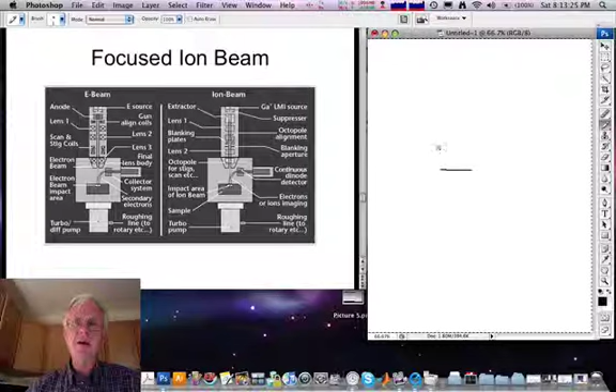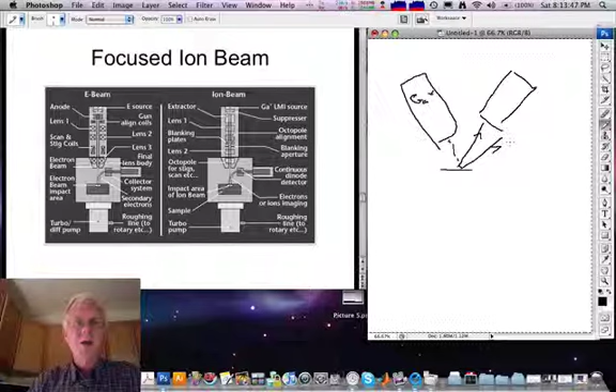And in the instrument that we have, they actually have two beams. So a sample sits like this, and then in one direction an ion beam comes down and mills the sample. So gallium ions, and then in another direction an electron microscope images the area being milled at the same time that it's milled. So the source of gallium is shown here. It's a little filament on which is suspended a gallium source in this container here, which is both heated and ionized to form the beam of gallium ions.